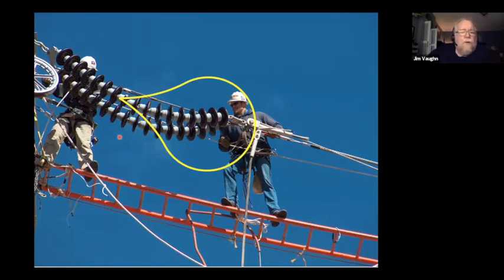Now, the yellow teardrop that you see here is there to mimic what happens along a string of insulators. The voltage collapses up the string. Now, this field of voltage collapses because of the insulating resistances along the length of this string. And as we move up, the voltage collapses uniformly. And that's created by the engineered design that creates a uniform collapse.